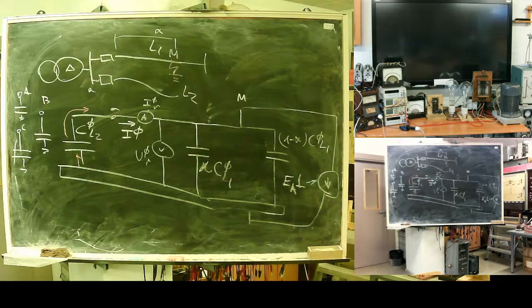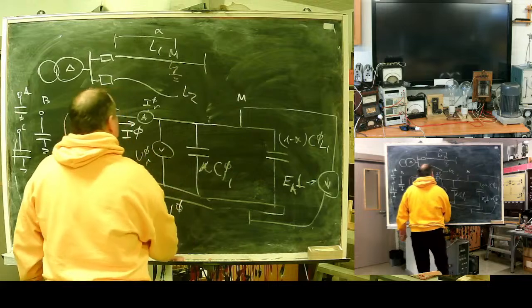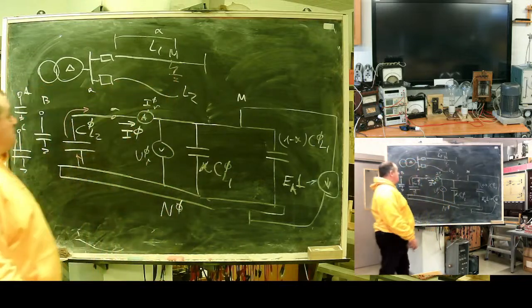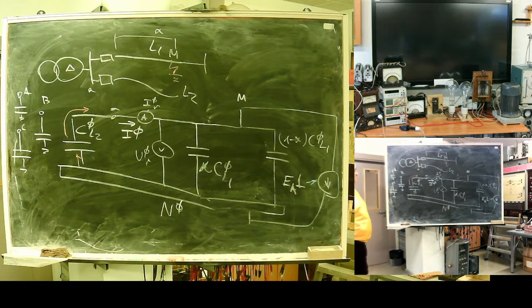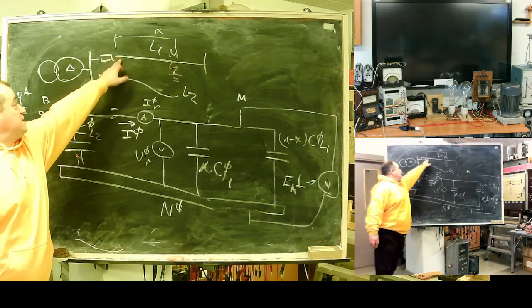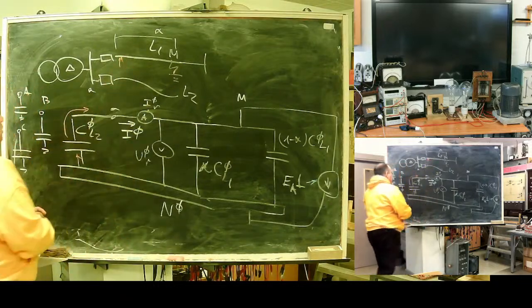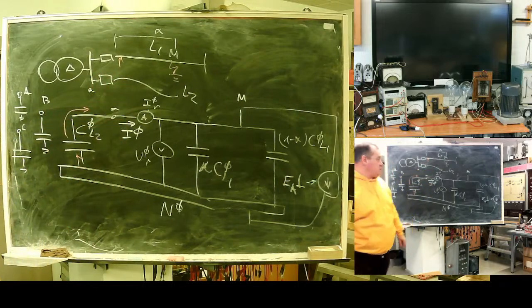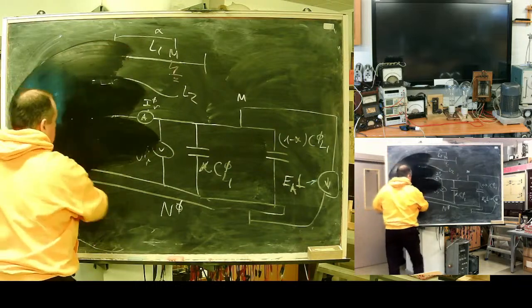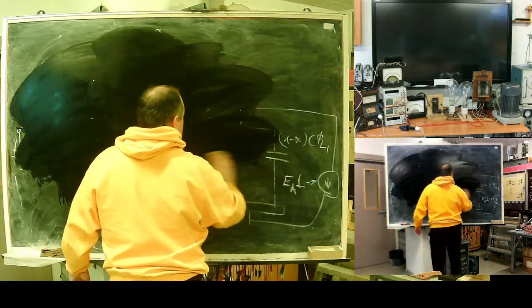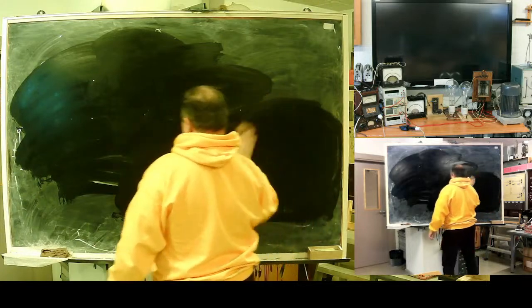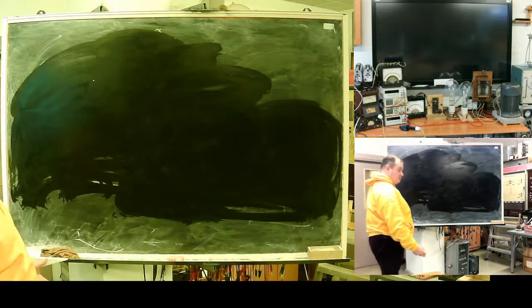it's useless to analyze such networks in phase coordinates, and we should switch to analyzing in zero sequence terms. Here I have two lines, one fault at a distance alpha per u, and a simplified zero sequence schematic shows us that the current through the relay, if the relay sits here, will be determined by the healthy part of the network. So what can I do? If I can't use current magnitude as a selectivity value, I will need to create schematics like this.